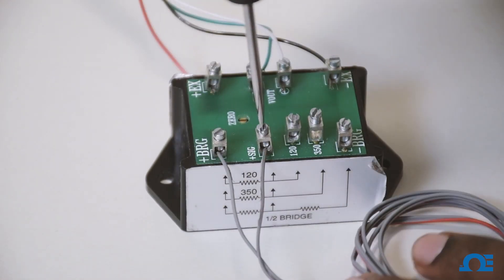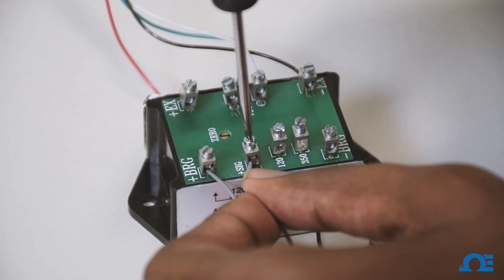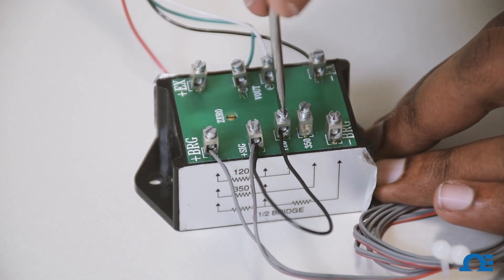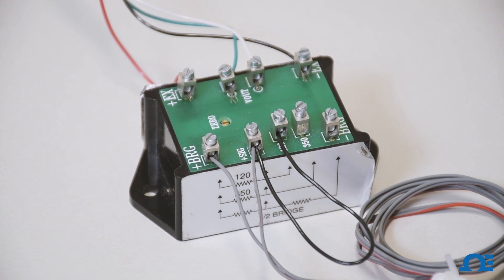The flying leads from the strain gauge connect to plus BRG and plus signal as indicated on the first schematic, and I have added a jumper between plus signal and 120 ohm. This is also listed in the BCM-1 manual.